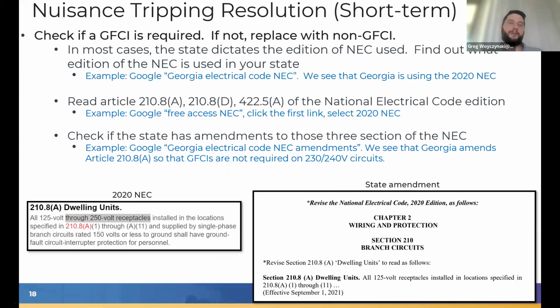Another short-term resolution. Check if a GFCI is actually required. If not, replace it with a non-GFCI. And this is something you can do in 10 minutes. You don't have to be an electrician. You don't have to be an electrical engineer. You don't have to be a code official to do this.